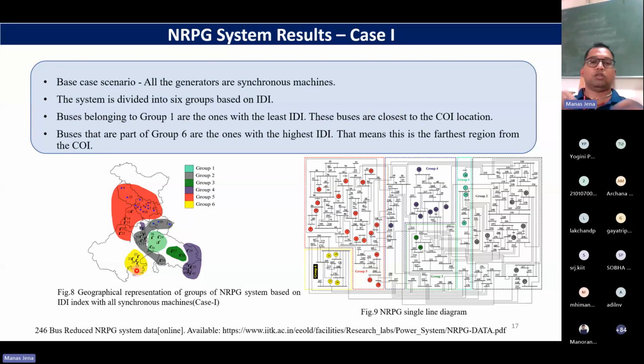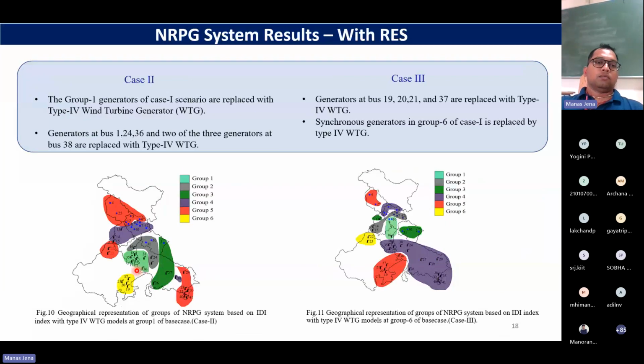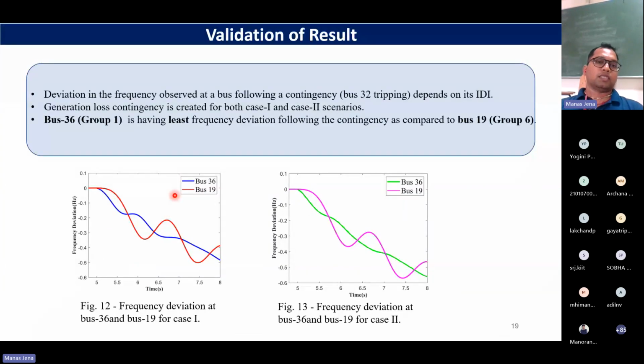Essentially we took buses from two extreme groups. Because bus 36 is staying closer to the COI, you can see that following the contingency, the deviations are less compared to bus 19, which is away from the COI, and that's how we validate the groupings.